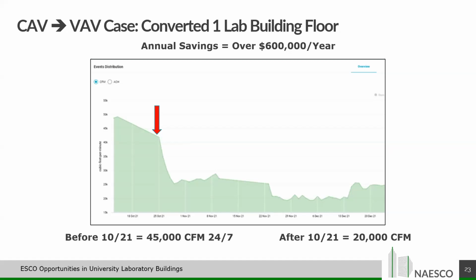One more pre-post case study, tremendous case study at a pharmaceutical in Cambridge, basically where we were able to reduce their exhaust CFM from 45,000 down to about 20,000 CFM. Again, there's two reasons for this. One is we're controlling the airflow, as discussed, where we're reducing that valve 85% when the sash is shut. But we're also reducing the position of the sash by our auto sash closer, which we'll get into in a second.